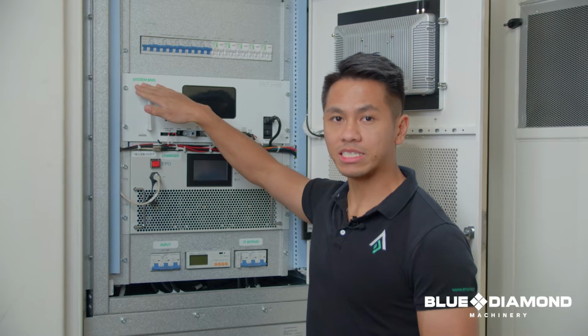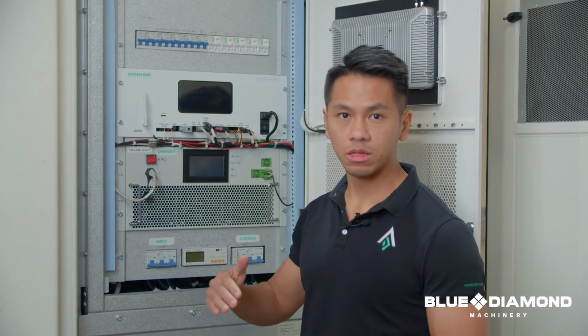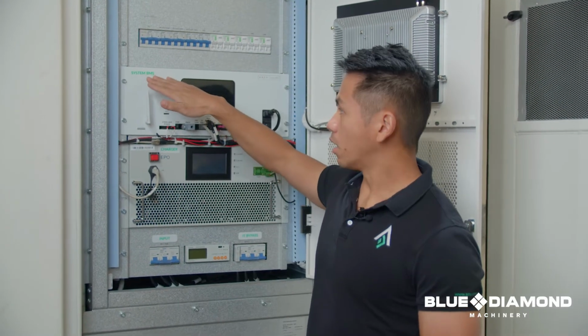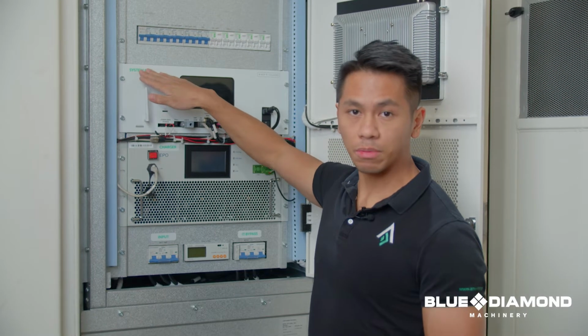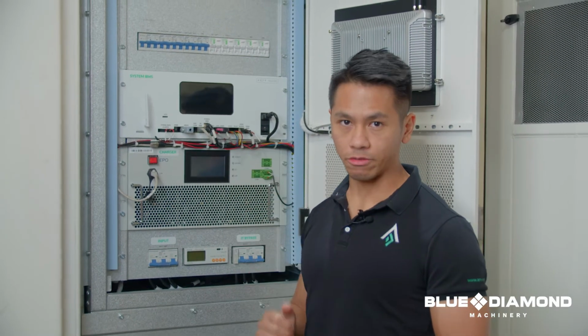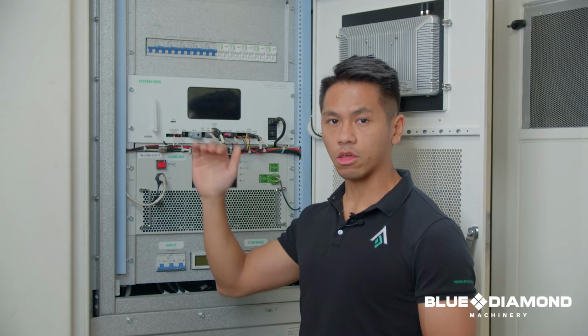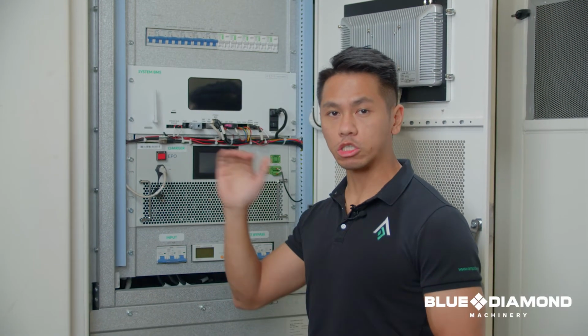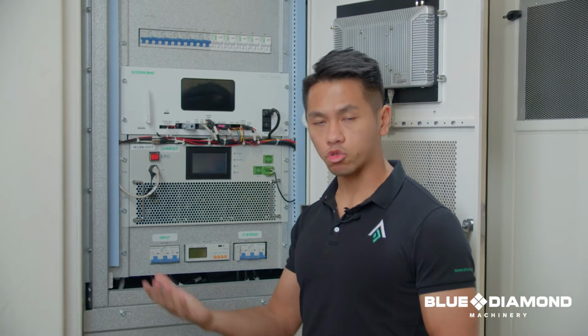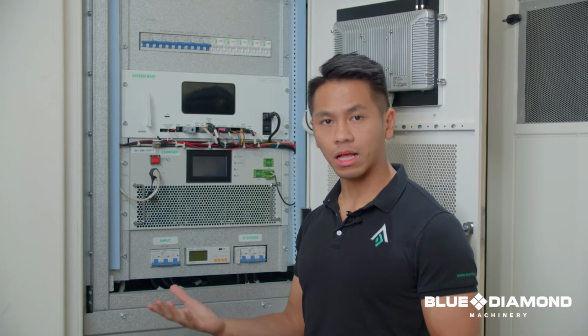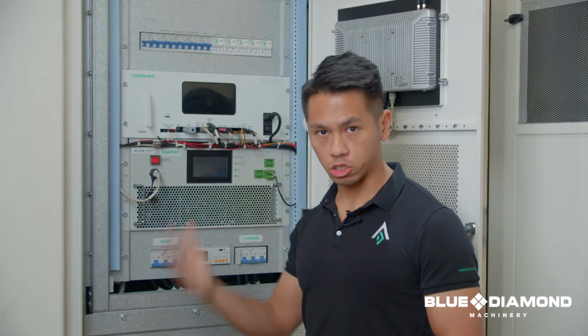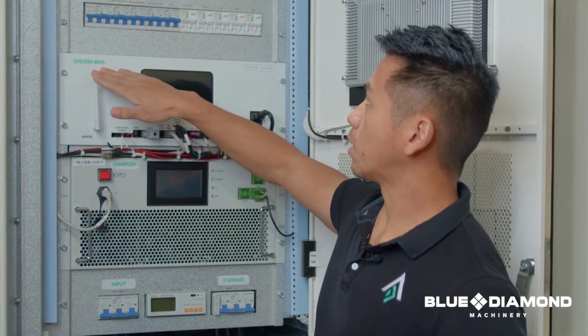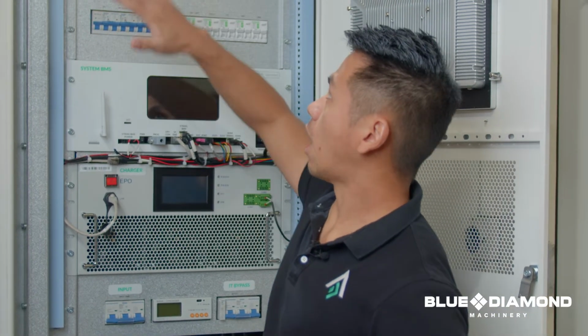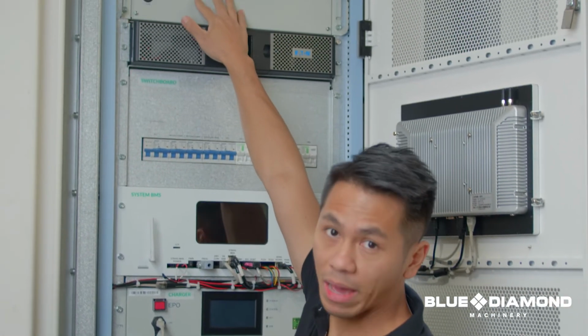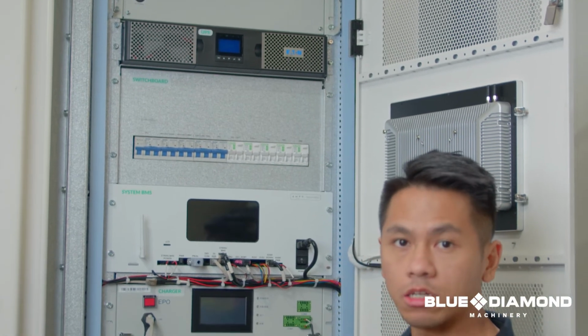Here we have a system level, or top level, BMS controller. Underneath it, the system BMS talks to string level battery management systems, and those string level BMS controllers talk to individual strings and individual modules or cells about how it should be charging up and discharging down. The system BMS then talks to other controllers such as the energy management system, the charger, and on the other side, the power conversion system.